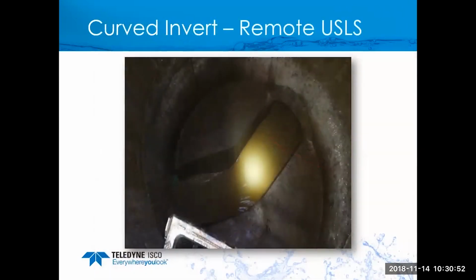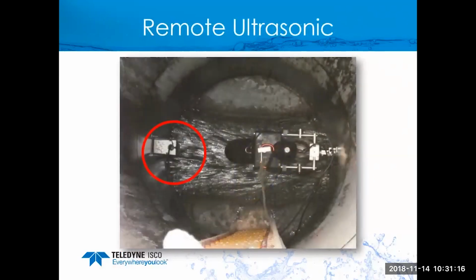Okay, more and more applications kind of like this. This is actually not a horrible one. We'll see a lot that are worse than this, and you'll have bends coming in from the pipe coming through the invert. You might get a 90-degree bend in there. Well, the laser needs to see the level in order to know where to focus. If the level is in such a way that it's hitting the bench, that isn't going to work. So what we're able to do is take that remote ultrasonic and mount it on the wall over your incoming line, and then we don't care really where the laser is sitting because it's going to focus into that pipe coming in. So now we're able to adapt to really, really bad conditions in the manhole.